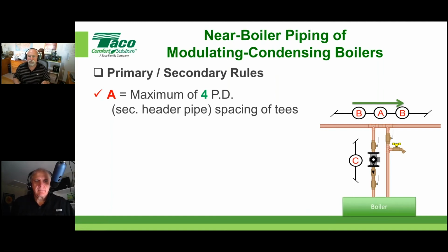So let's do this together. If we say the maximum is 4 pipe diameters of this secondary header here, okay, and that secondary header was 2-inch, then you'd say, oh, that would be 8 inches, 2, 4, 6, 8, right? So I don't want it to be any more than 8. Again, don't worry about that. Understand the concept. What we're trying to do is make sure those two T's are as close together as possible.